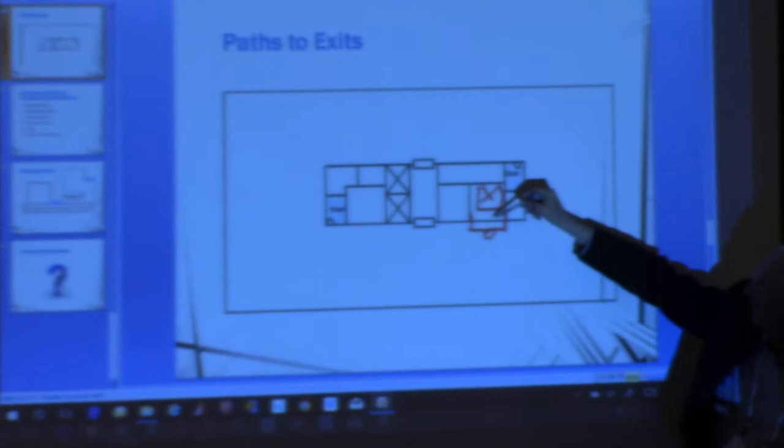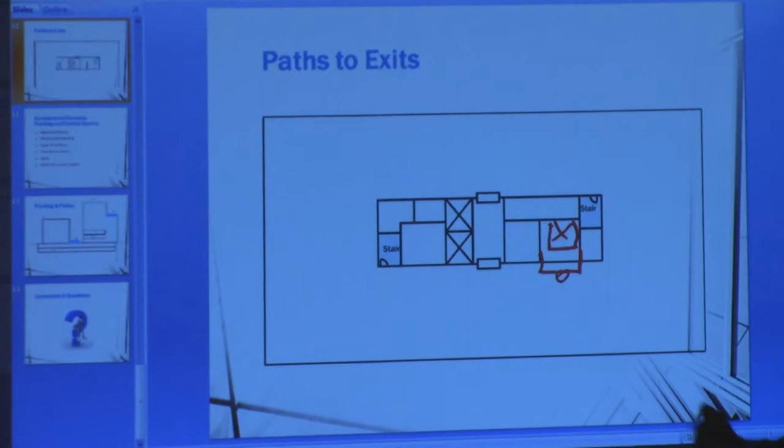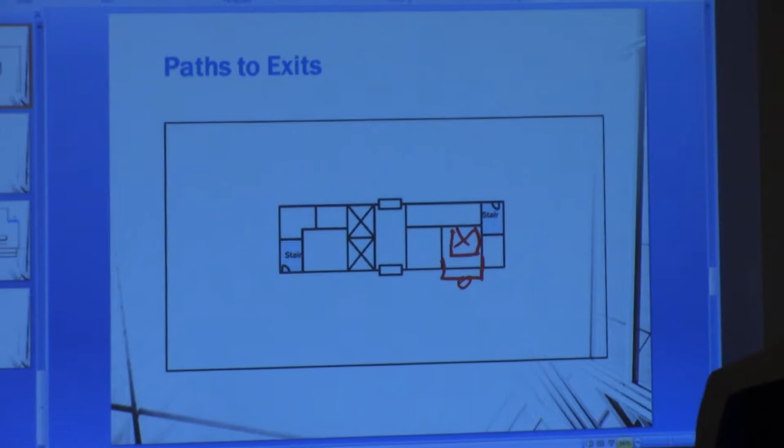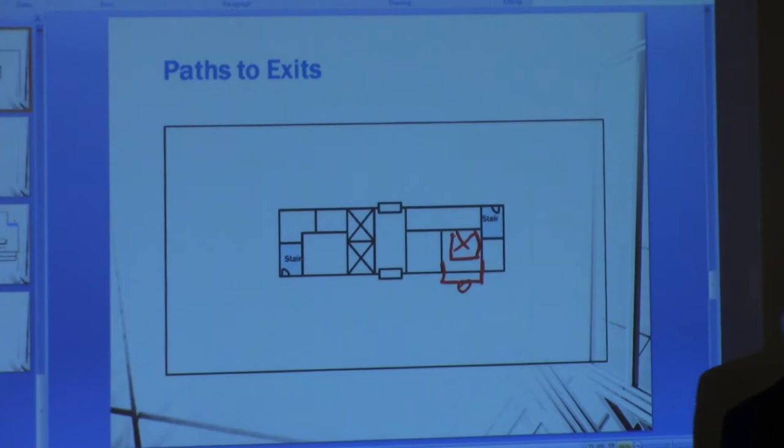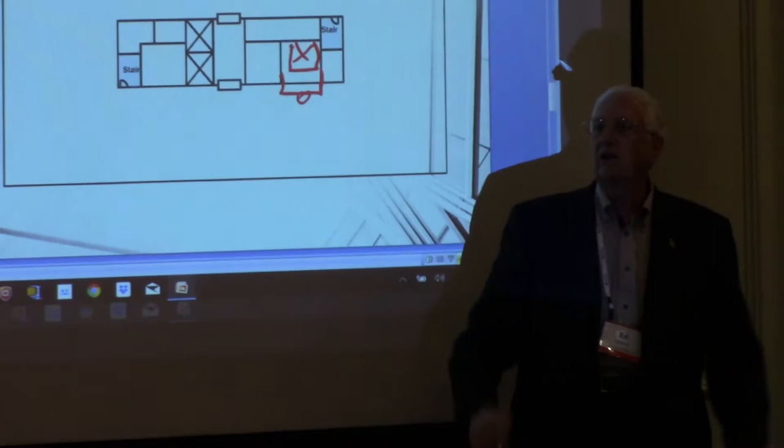How many times do we see this — a great elevator with a vestibule and a door, and people want to lock it from the inside out? You can't do that. You've got to be able to get out of it. And if you're locking the egress side of that door, you're in an access-controlled egress door situation with all its requirements. This makes it pretty pointless because a PIR sensor in such a small space would unlock the door the moment you step out of the elevator anyway.